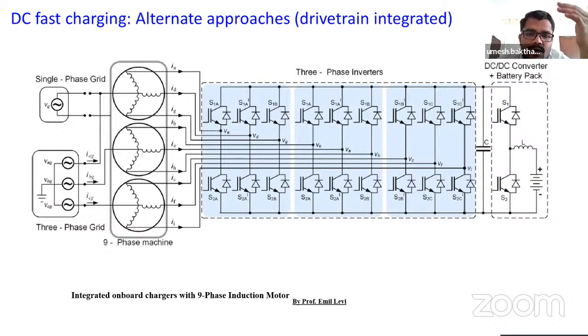If you carefully observe, there are 3-phase winding groups. The first winding group is 0, 120, 240. The second is 40, 160, 280. So there are 3-phase groups, and each has a neutral. They have separated the neutrals, and to each neutral they give one line, like A phase given to the neutral of the first 3-phase group.